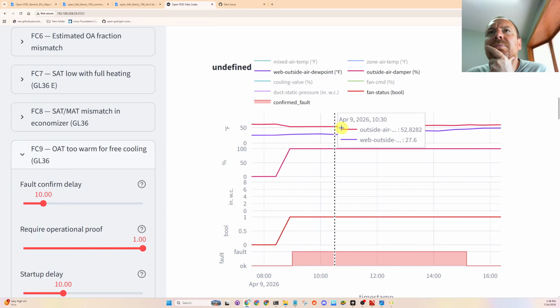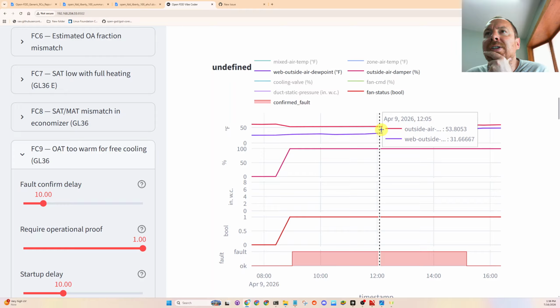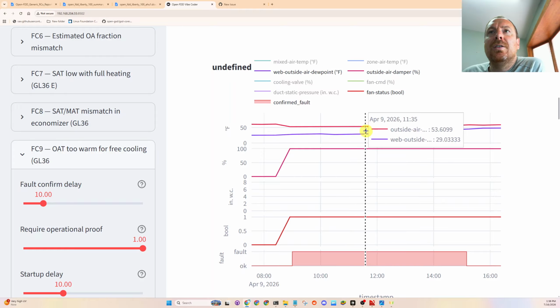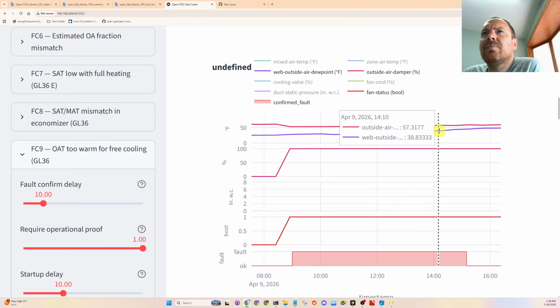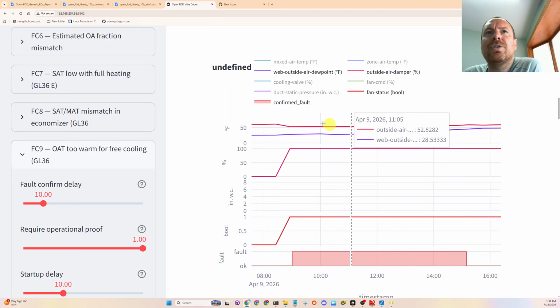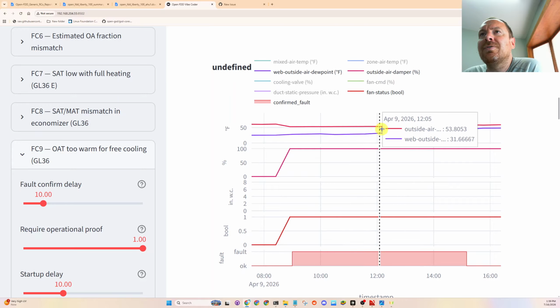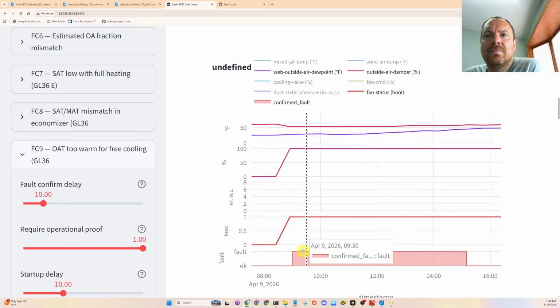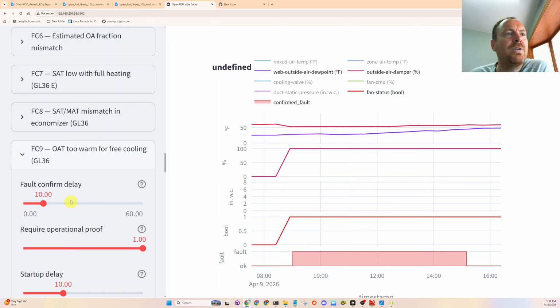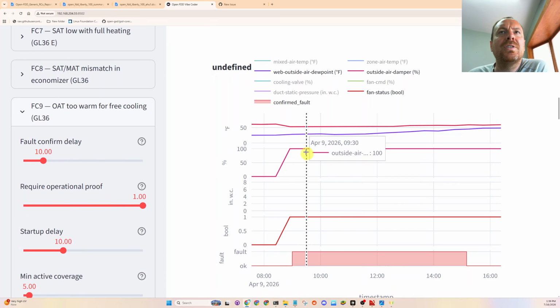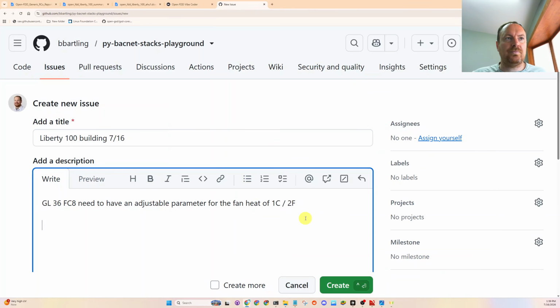Something's not right here, because this looks like excellent weather for, excellent conditions for free cooling. Our dew point is way below 60, and our outside air temperature is only 53 degrees. Okay, so we have something wrong here. I'll have to look into this.